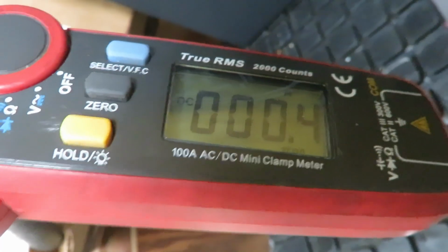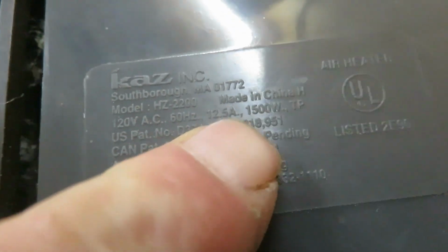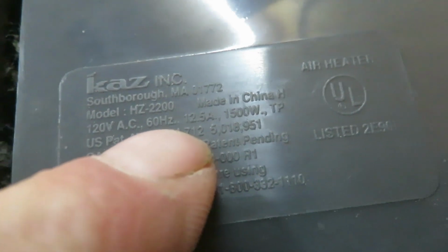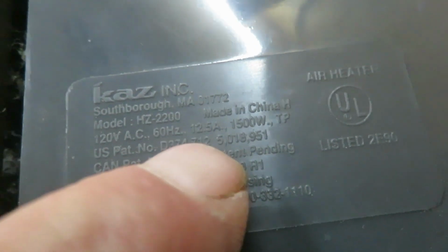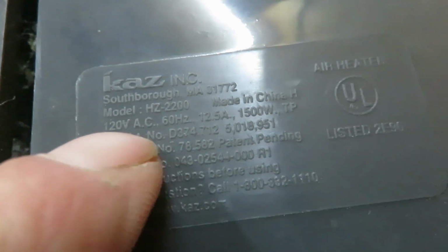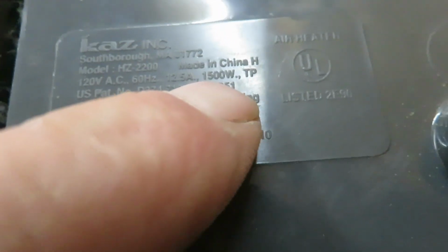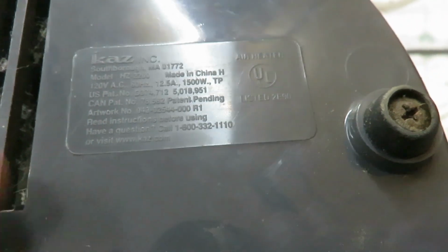So I will get a load put in here and see what it does. I'm going to put this space heater on. The rating says, I don't know if you can read that, but right here it says 1500 watts, 12.5 amps at 120 volts, and 1500 watts should be the same between both AC and DC side. We'll try it and see what it says.